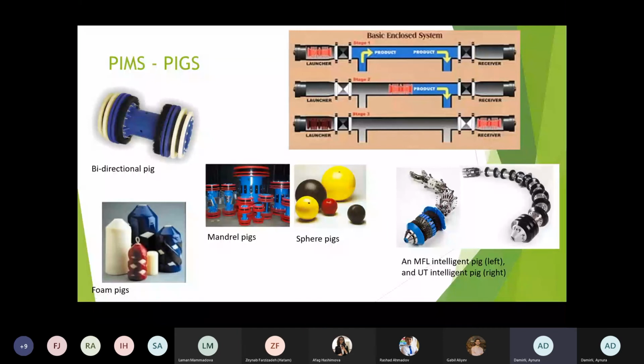So this is for cleaning, repair, and moving inside, like a wax removal process, targeted pig types. And the rest you can see here, we call intelligent pigs. This is not just moving inside, it's inspecting inside. There are sensors, ultrasonic sensors, which while moving inside the piping take measurements and provide us the condition of the pipeline, and if there is any wall loss, like metal loss, internal or external, it gives us signals, and we can exactly find where there is metal loss in the pipeline. And the first one is magnetic flux intelligent.